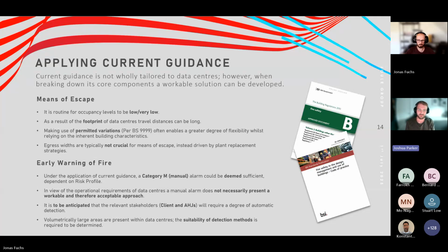So how do we apply current guidance? As we mentioned, current guidance is not tailored to data centers, but when we break down the constituent components which form a data center, and look at the particular risk associated with those areas, be that fuel storage areas or diesel generators on the gantries, for example, we look to apply known principles within that guidance to address those areas in isolation, to then form a wider fire safety approach for the building.